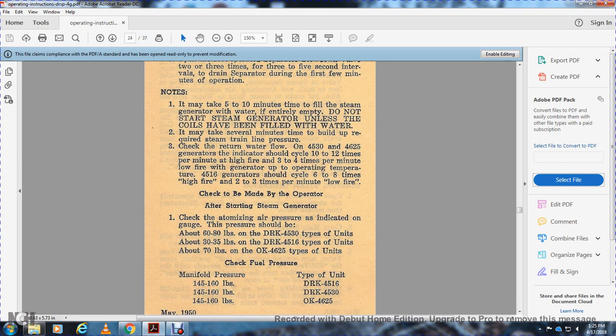Checks to be made by the operator after starting the steam generator. Check the atomizing air pressure indicated on the gauge. The pressure should be about 60 to 80 pounds for the DRK 4530 type units, about 30 to 35 pounds for the DRK 4516 type units, and about 70 pounds for the OK 4625 type units.